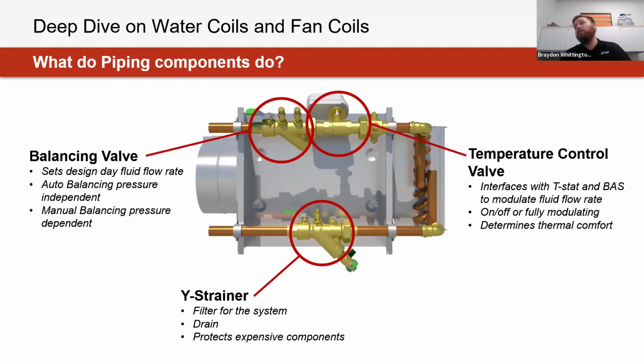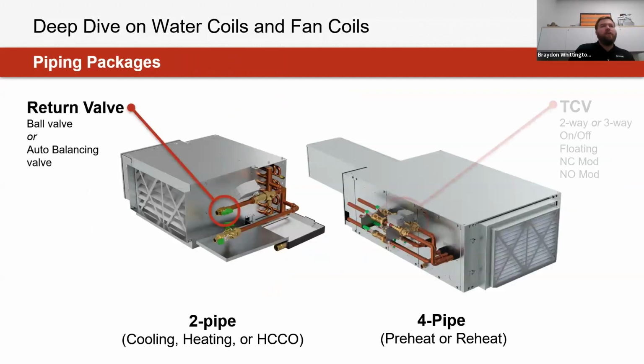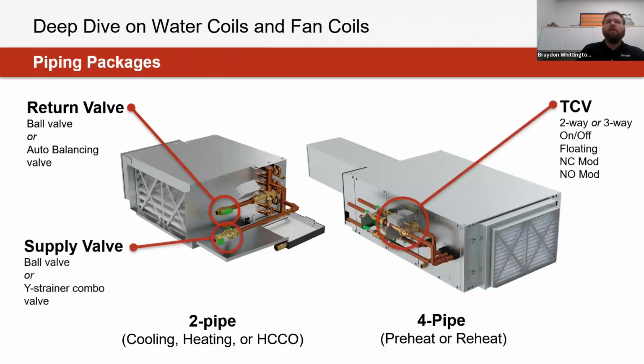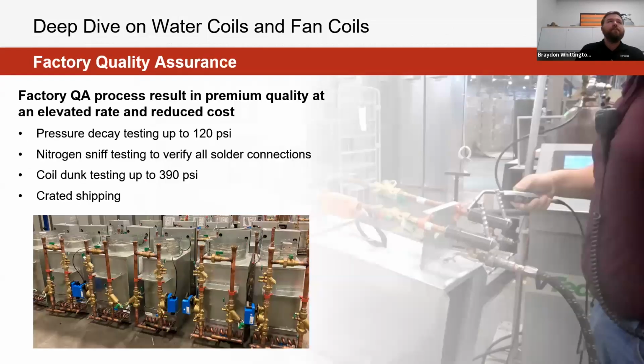And then some form of blowdown valve or strainer, for when we want to filter unwanted particles that might try to pass through our coil, so we'd be able to get those out when doing maintenance on the coil itself. This also allows for different options, and more commonly we'd see this paired with fan and blower coil equipment, to ship as a full package with all these different components for both 2-pipe and 4-pipe configurations.